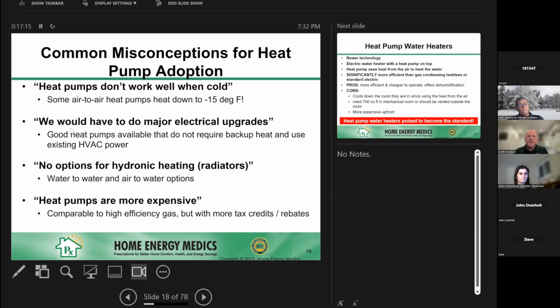Another misconception is that we can't go the heat pump route because we have to do a ton of electrical upgrades. That's not really true either. Some good heat pumps out there don't even require backup heat, which is where you'd use electric resistance and that's where all the power is demanded. You can use existing HVAC power where a gas powered furnace and AC condenser are already outside, in a typical forced air split system.